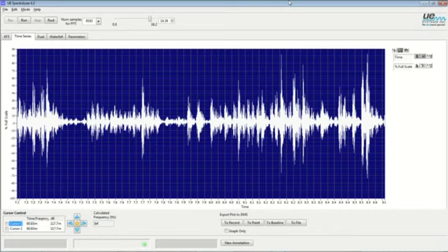Okay. Well, they'll write in if that didn't answer it. And another question, can you set up a predictive timeline for scheduled replacement? To be able to predict anything as far as replacement is difficult. My recommendation and the way we approach it, it all depends upon the severity of the event. In this case, yes, we focused a lot on tracking. The key thing to remember about tracking, it's destructive. It starts to degrade the insulators, and it is only a matter of time before it fails. Nobody can predict how much time.